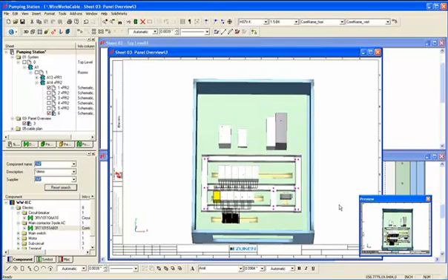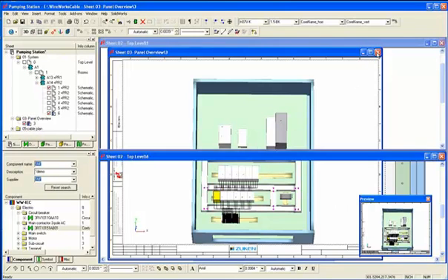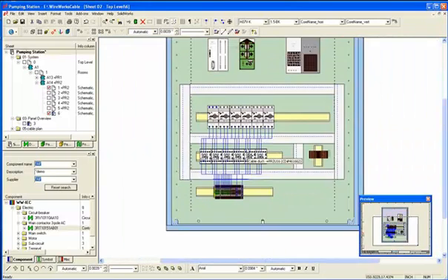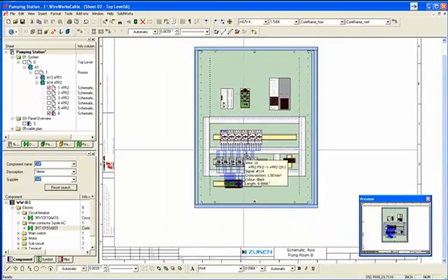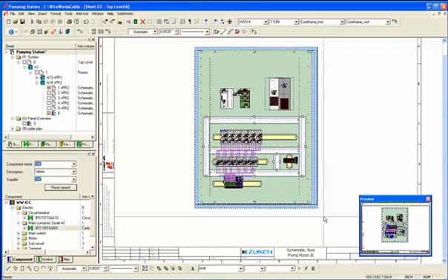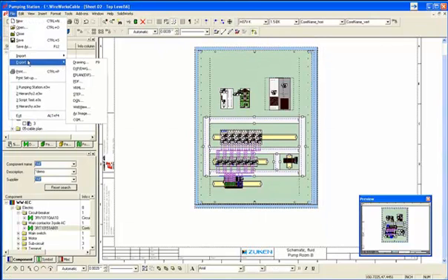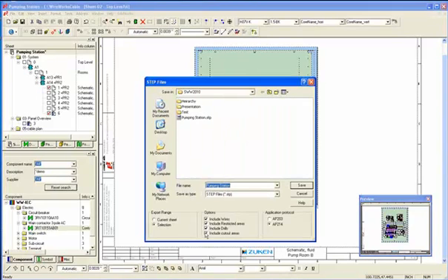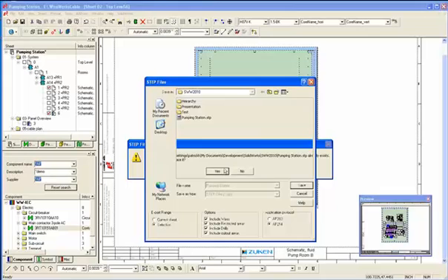So for the electrical engineers, there is no real need whilst doing panel design to go into the panel, but where we will need to go into the panel is where we transfer the information from WireWorks into our 3D model for envelope and space requirements within the panel design. So if I select all of this box here, go to my file and export that as a STEP file, we can save all the elements, including the wires if we want to, any drill breakouts, restricted areas, callouts, and I'll save that into here.